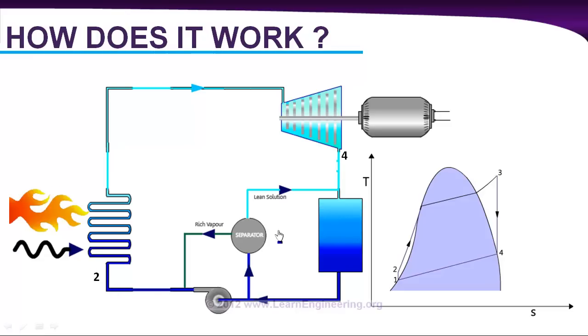After this point 4 we are rejecting heat to the surrounding, and after this point 2 we are absorbing heat from some external agency. So why can't we supply some amount of heat from point 4 to point 2, which will save some energy and will obviously increase the power plant efficiency. That is exactly what we do here.